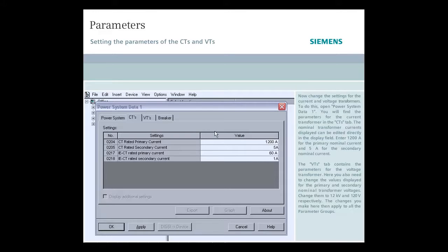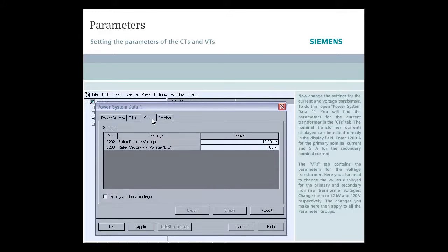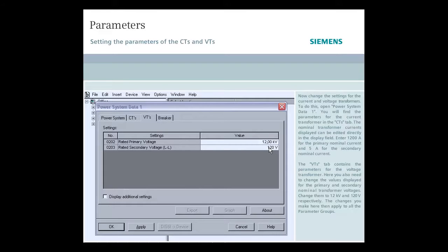The VTs tab contains the parameters for the voltage transformer. Here you also need to change the values displayed for the primary and secondary nominal transformer voltages. Change them to 12 kV and 120 V respectively.